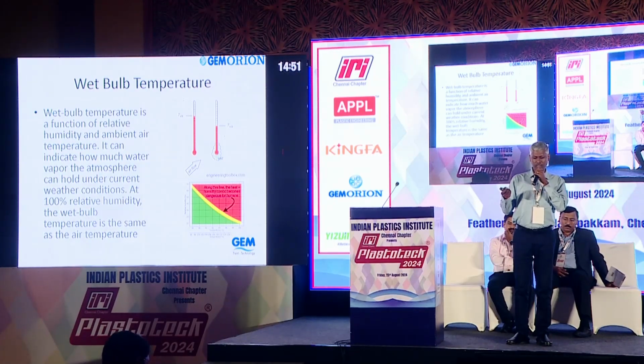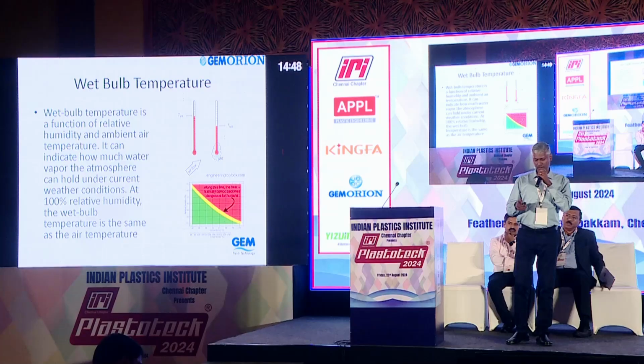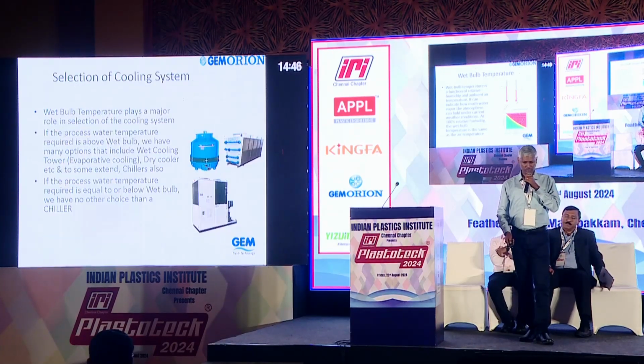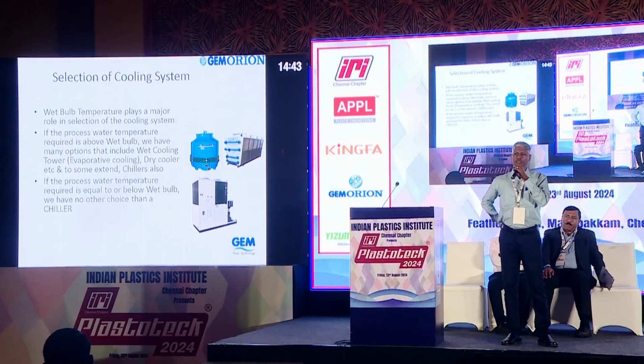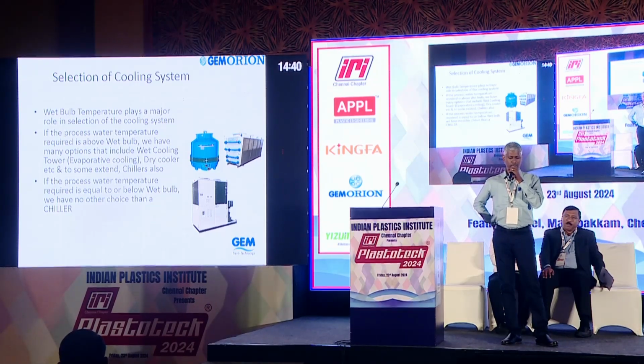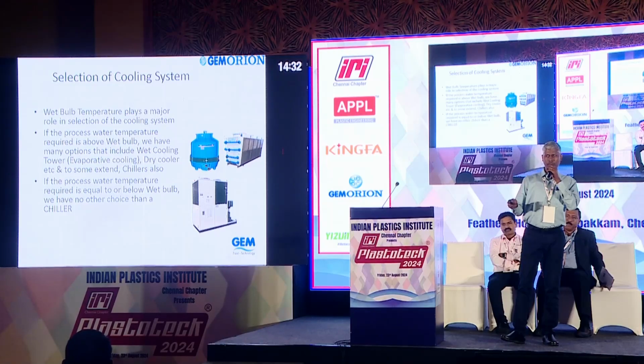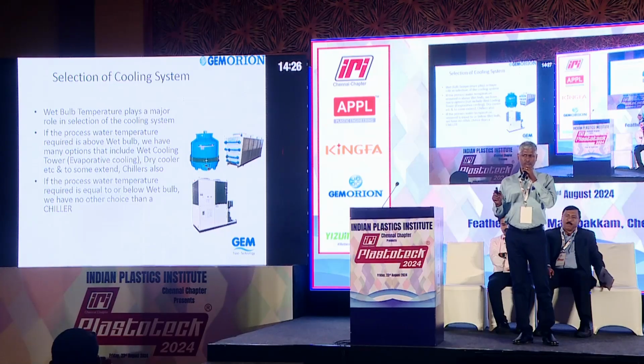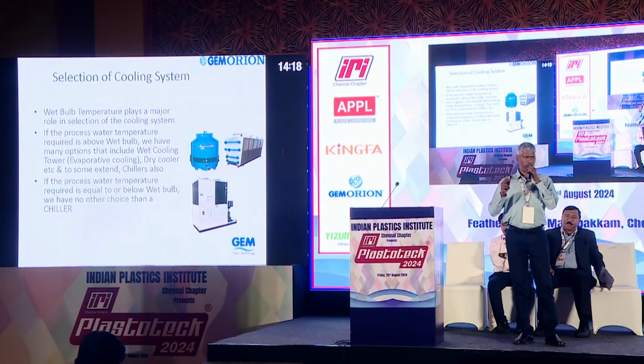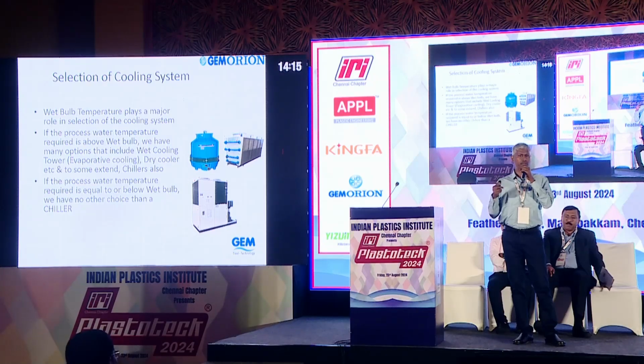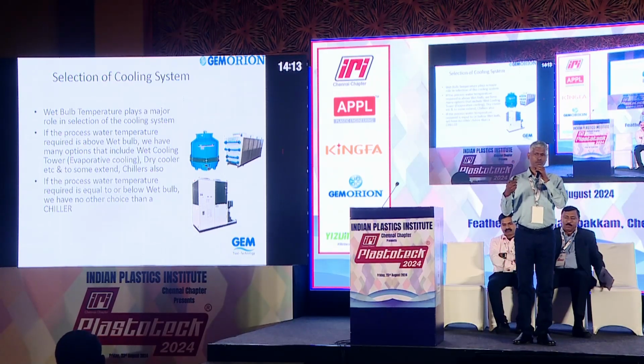The measurement is very easy, with the help of a small thermometer and a wet cotton wick on it, we can measure the wet bulb temperature. After measuring the wet bulb temperature, we decide on the cooling system based on it. If you want to cool the media, say water or a mixture of water and glycol, to a temperature above wet bulb, you can go with a simple cooling tower, which is the most economical way of cooling. If you want to cool the water or media to the level of wet bulb or below, you have no other choice, you have to go with some refrigeration-based technique or a chiller.